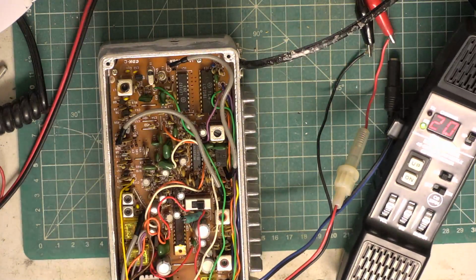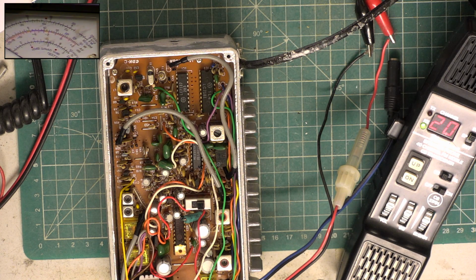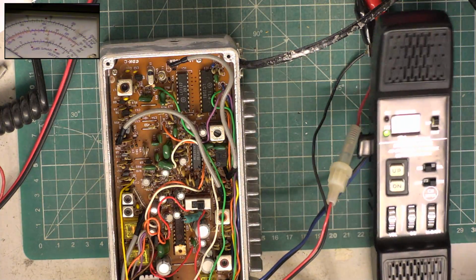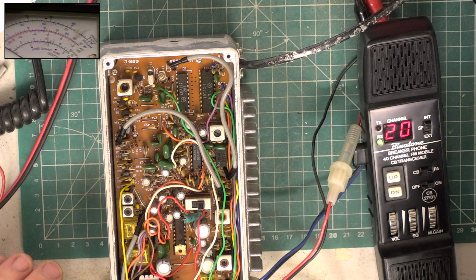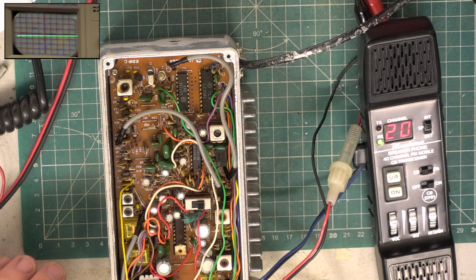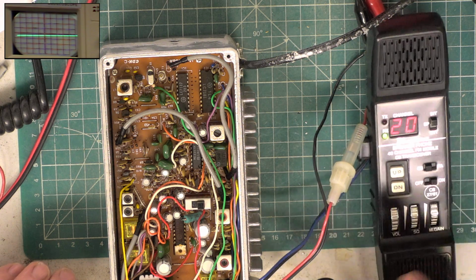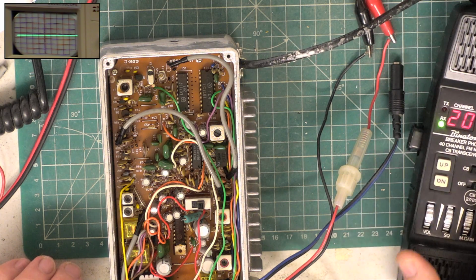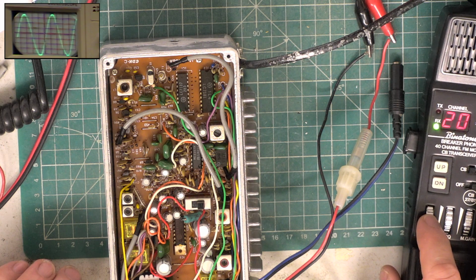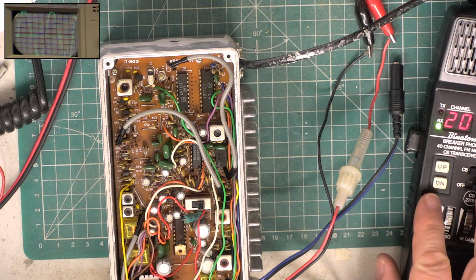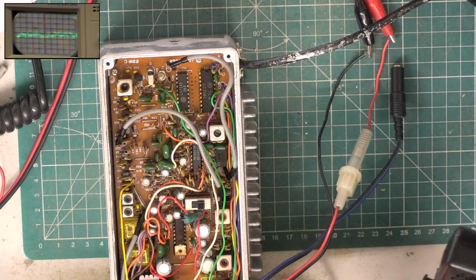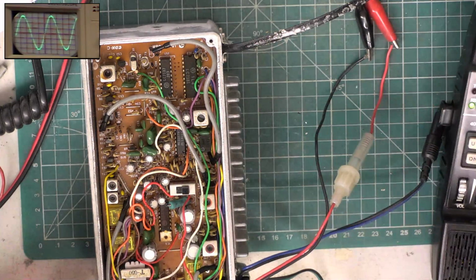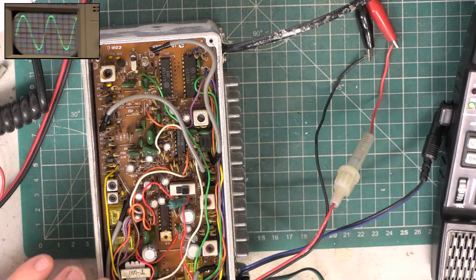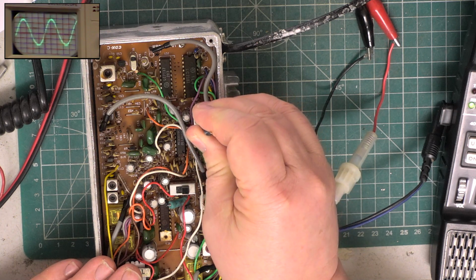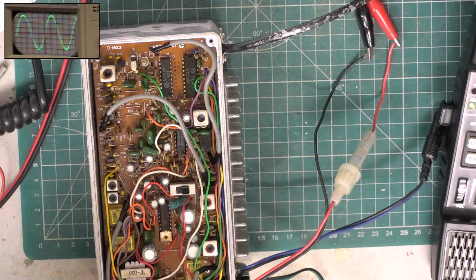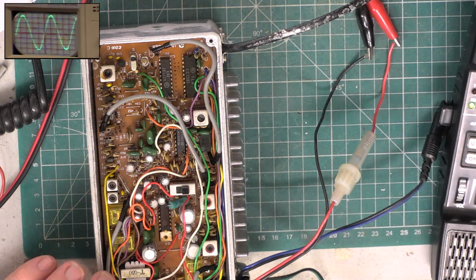I'm going to just see if we've actually got picture-in-picture on. We haven't. Right. Here we go. Let's put the camera on there. Switch to external. We've got a dirty volume control. Okay, so we'll just peak transformer 6. Very minutely out there. Now we'll drop the signal and put the SINAD meter on instead.